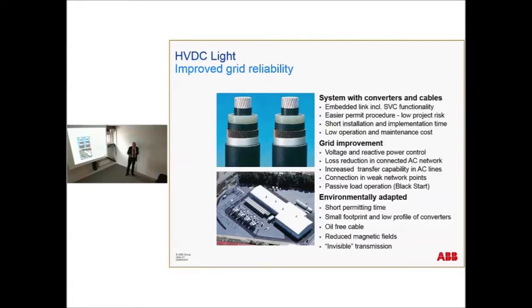And when you have a DC link, you will also have reactive power or SVC functionality, since that is inherent in the HVDC Light converters. And it's possible to build what we call invisible transmission by using these HVDC Light cables, and we can have these stations in a building, looking like a barn or something like that.